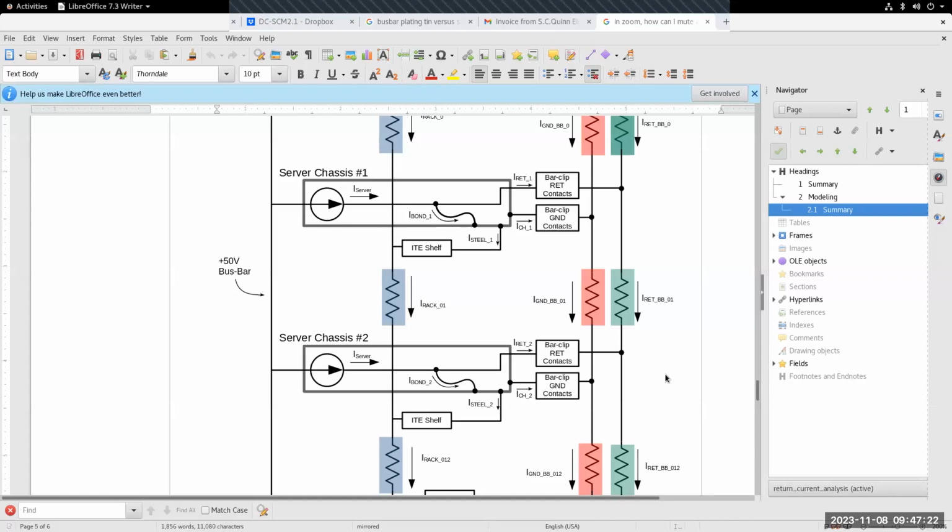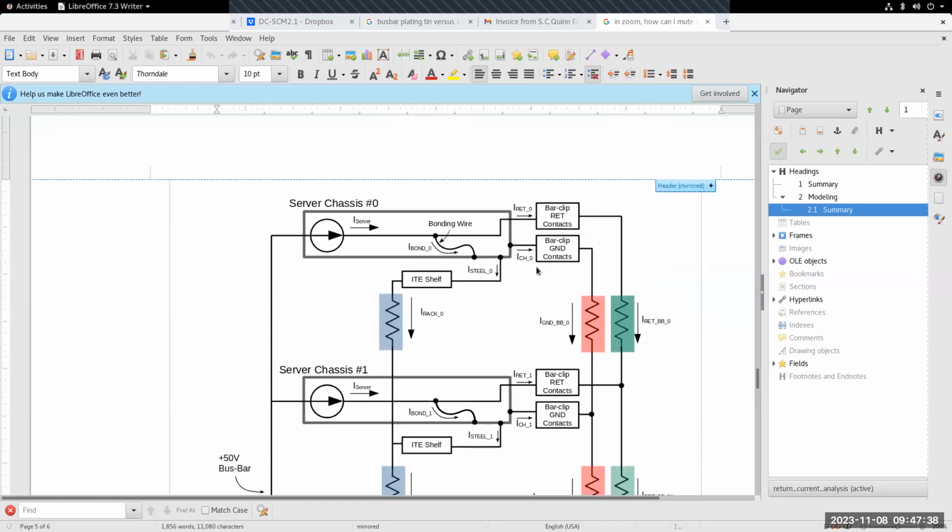Yeah, and I don't have enough. So we're early here in our ORV3 journey, but I don't have enough shelves, I don't have enough loads, and we're trying to acquire the hardware we need to collect better data. But when you say you're seeing 25 to 30% flowing in the steel, well, how does it get back? Well, that's what we're trying to figure out yet.